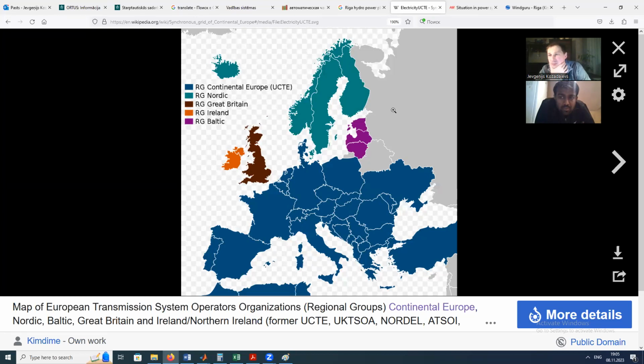As I said, this is a political decision, but let's discuss from the technical point of view how this could be implemented. First of all, to make this synchronization, we need a physical connection, to build physical lines to connect Lithuania to Poland. This was made, the interconnection to Poland. But there are some disadvantages to such a solution. First of all, we have a deficit on one hand, and we need to keep the balance on the other hand, and the frequency - we should be synchronized to this system.